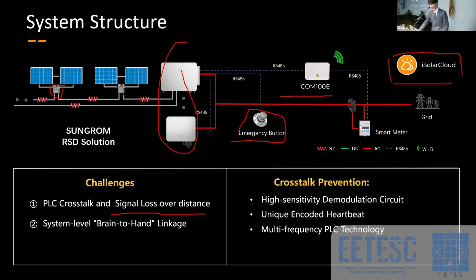So even when the signal travels 300 meters and becomes extremely faint, the circuit can act as a dialogue ear to filter out the noise and amplify the heartbeat signal, ensuring a stable connection. And another one is PLC crosstalk. To tackle the crosstalk, as you can find here, we use the unique encoded heartbeat and the multi-frequency PLC technology. This one is easy to understand. We put more bandwidth on the communication, making it more reliable.